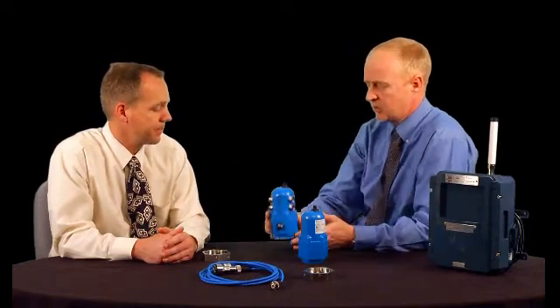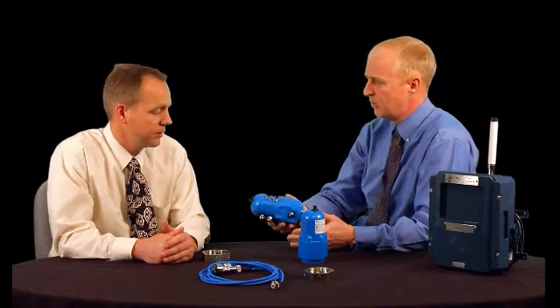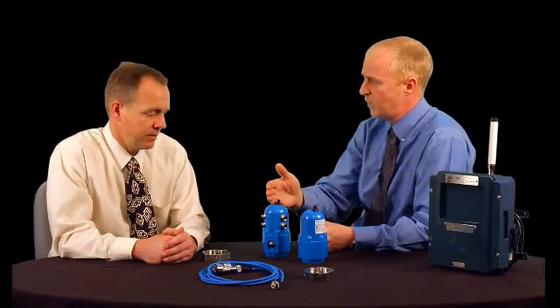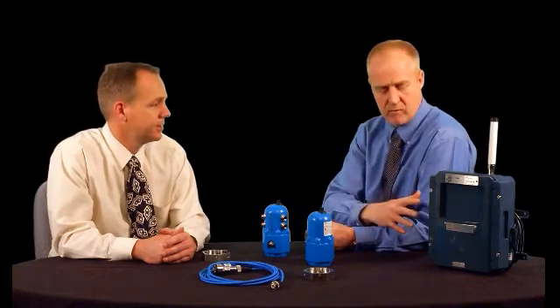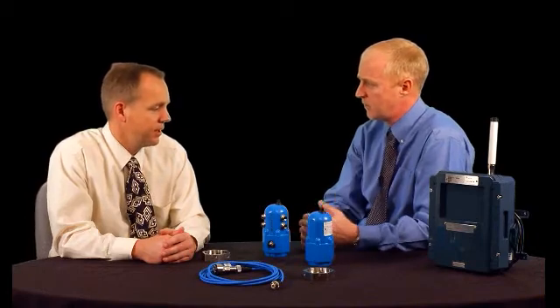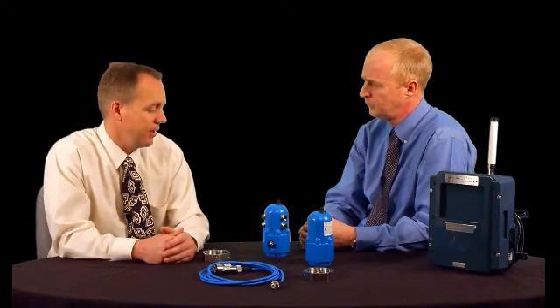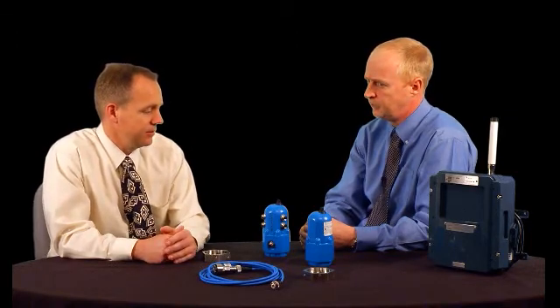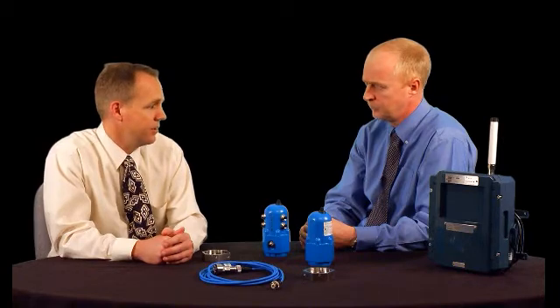The design with the cables going out to the accelerometers means this unit could be located far away from the actual motor if needed — it doesn't have to be vertical, it could be horizontal. You can run the accelerometers to the location of the bearing and bring the data back into this unit. From there, it's meshed to other items like the repeater, which goes through to a gateway. The gateway we're showing today is the Yokogawa Gateway. The Yokogawa Gateway is part of the ISA-100 standard and is designed to operate with any ISA-100 compatible device. The WSIM and the EssentialInsight platform are ISA-100 compliant, so you can drop a WSIM and System 1 onto an existing ISA installation or participate in a greenfield application where a new network is going in.